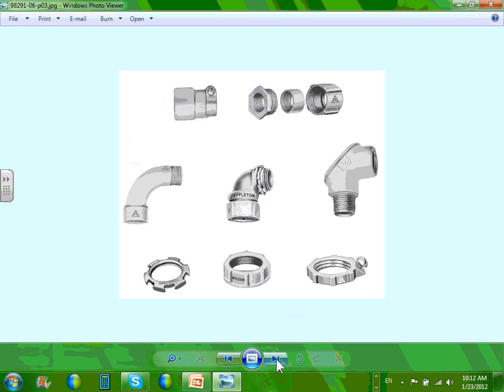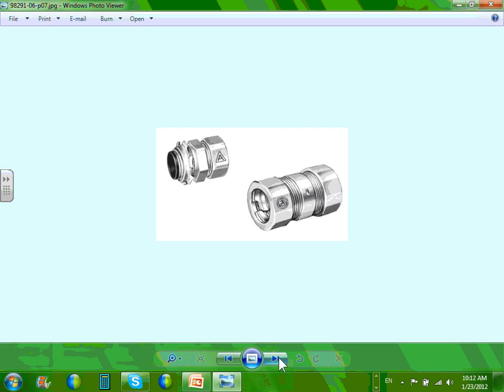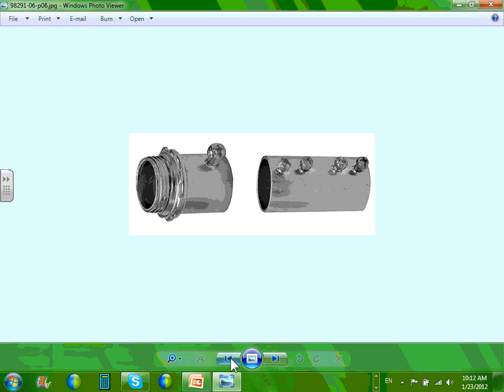A couple of things, guys, about fittings for threaded conduits. Okay, connectors. This connector, guys, since you're using EMT, please get used to it. Here's a connector right there. They call it a set screw connector. 90% of the time you're using set screw connectors with EMT. That's the connector and the coupling that comes with an EMT conduit, always. They call it set screw because you have set screws and you tighten them from both sides.